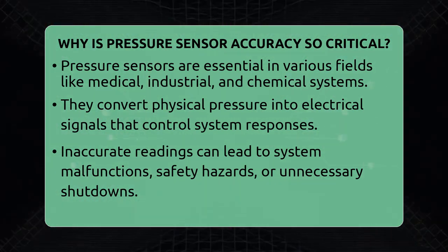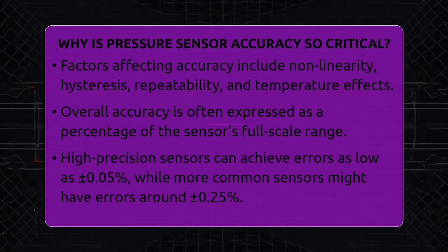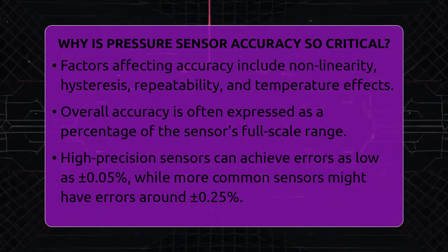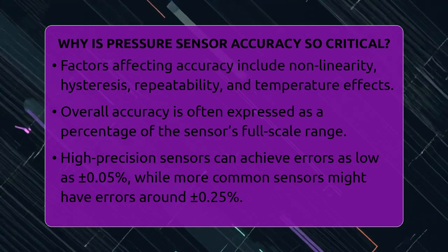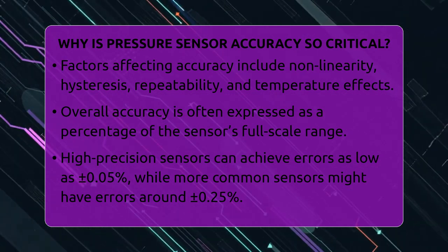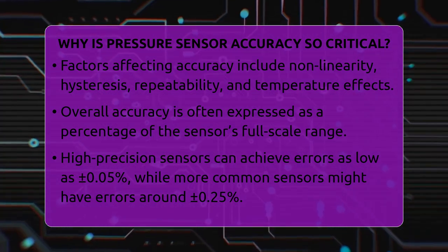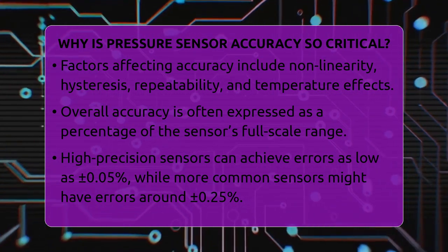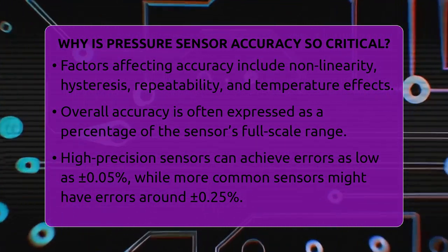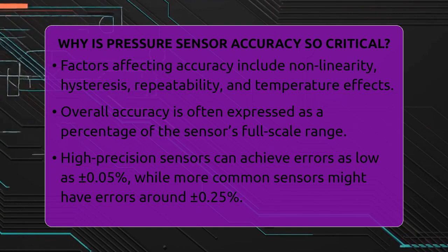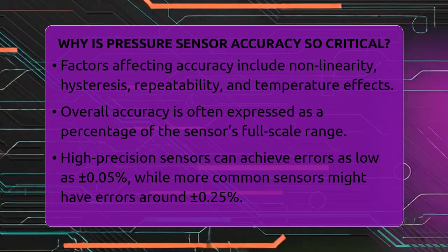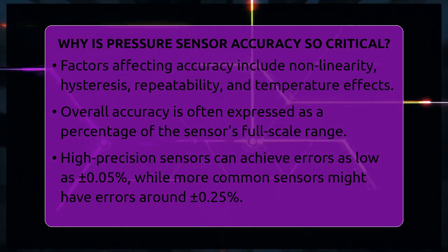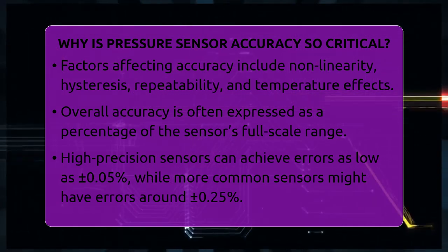Accuracy depends on several factors. Non-linearity is how much the sensor's response deviates from a straight line. Hysteresis is the difference in readings when pressure is increasing versus decreasing. Repeatability measures how consistent the sensor is under the same conditions. Temperature effects can also influence readings, especially if the sensor isn't temperature compensated.